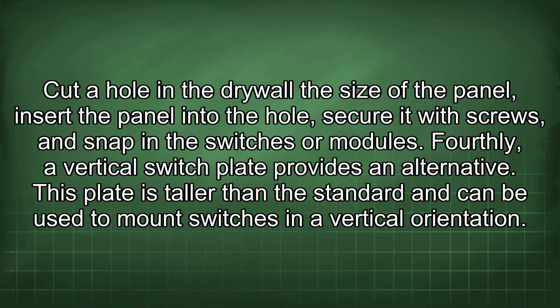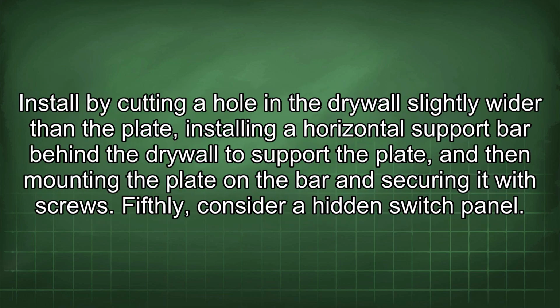Fourthly, a vertical switch plate provides an alternative. This plate is taller than the standard and can be used to mount switches in a vertical orientation. Install by cutting a hole in the drywall slightly wider than the plate, installing a horizontal support bar behind the drywall to support the plate, and then mounting the plate on the bar and securing it with screws.